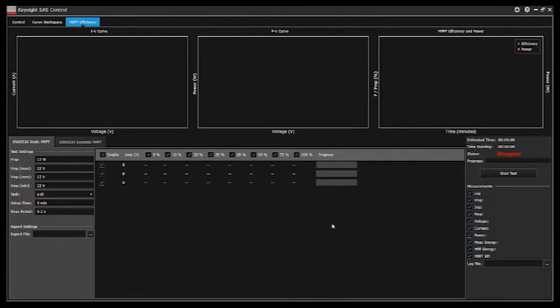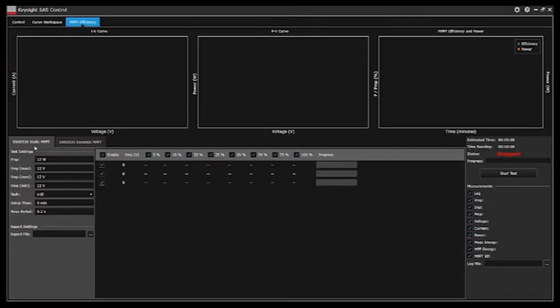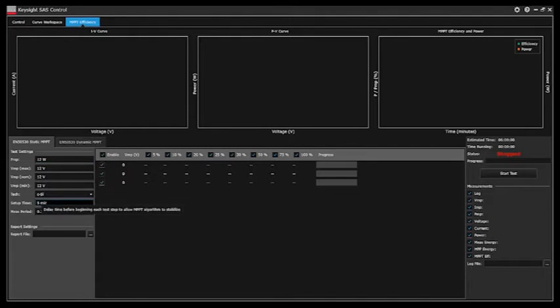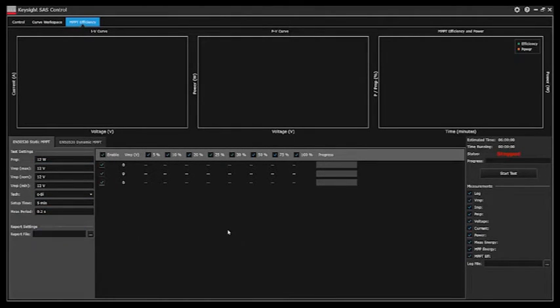Now that we have a trial of the pro version we can run the full EN 50530 static and dynamic test. Here in the static MPPT test tab you can see that we have test settings here on the left. You can set all of these test settings as well as select a report file and start the test.